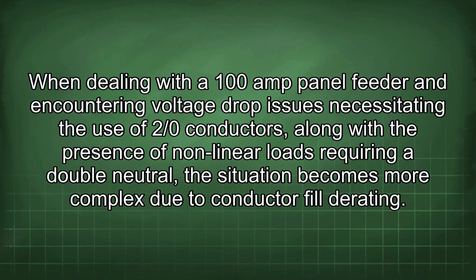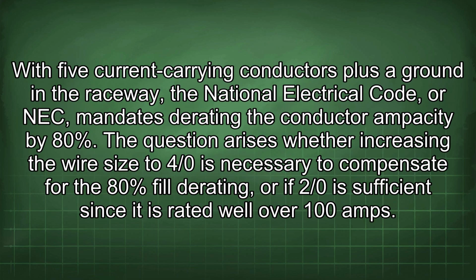When dealing with a 100 amp panel feeder and encountering voltage drop issues necessitating the use of 2/0 conductors, along with the presence of nonlinear loads requiring a double neutral, the situation becomes more complex due to conductor fill derating. With 5 current carrying conductors plus a ground in the raceway, the National Electrical Code, or NEC, mandates derating the conductor ampacity by 80%. The question arises whether increasing the wire size to 4/0 is necessary to compensate for the 80% fill derating, or if 2/0 is sufficient since it is rated well over 100 amps.